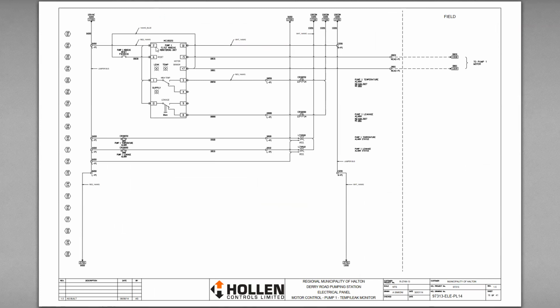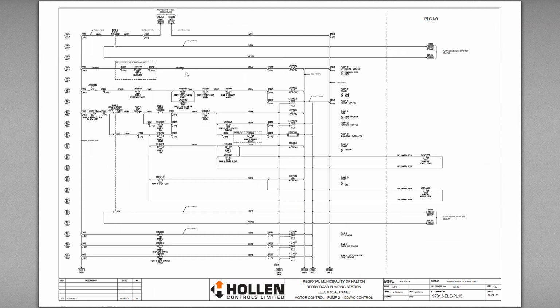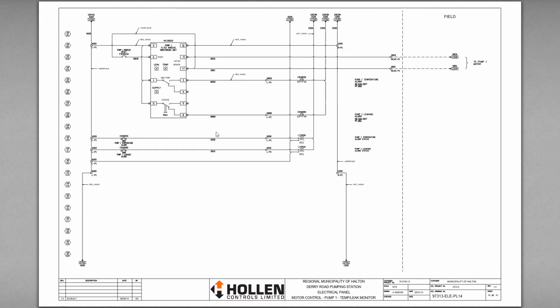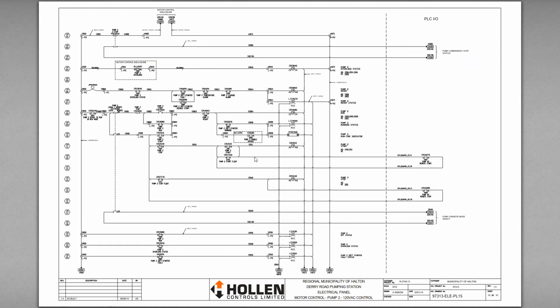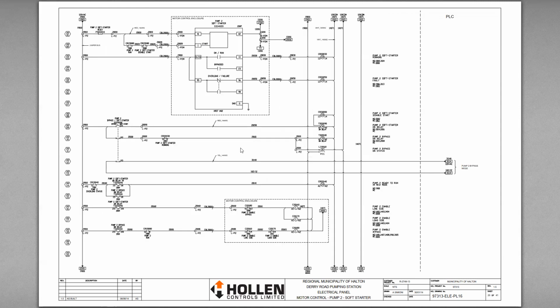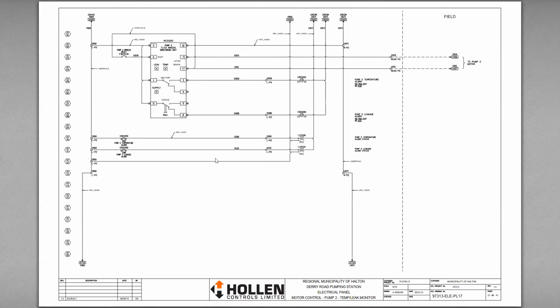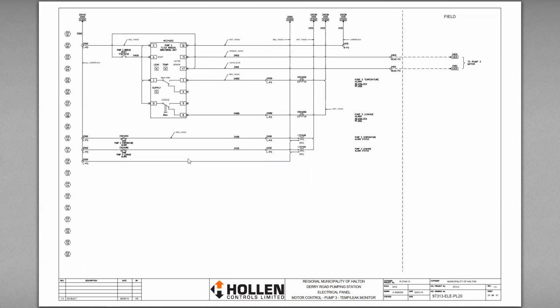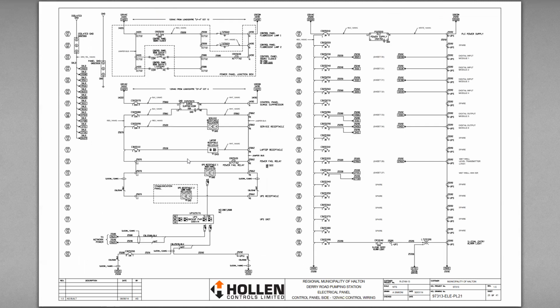You have overheat sensors because these pumps are underwater. They have special Flygt MiniCAS monitoring relays that are wired in a specific way, which is captured in these drawings with their reset. More motor starter circuit, more motor starter circuit, lots of motor starter circuits.